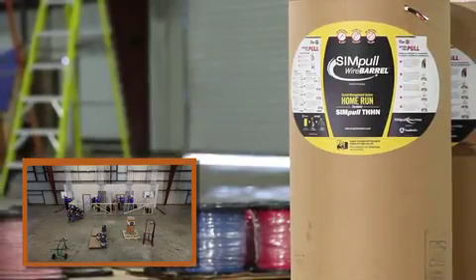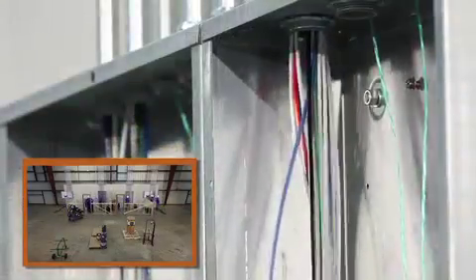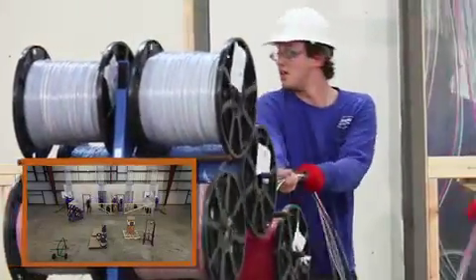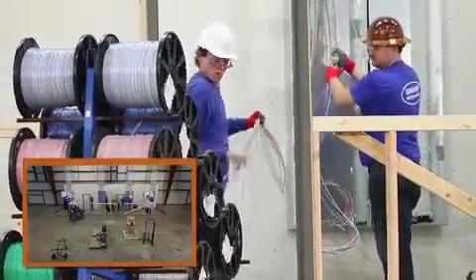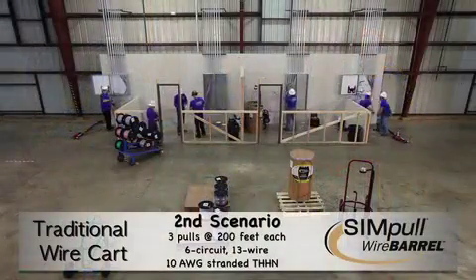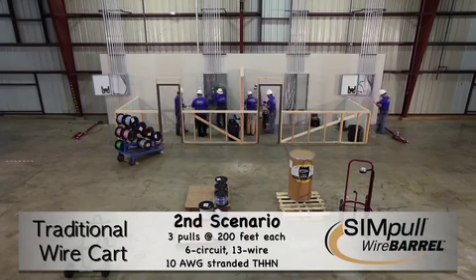During more extensive pulls, using the SIMpull WireBARREL system provides a fluid, consistent way to ensure all conductors are even and easy to group together as they are fed into the conduit. With the wire cart method, an extra man is needed in an attempt to create an efficient pull and keep the wires even as they are pulled off the reels and fed into the conduit. Considerable effort is required to pull the wire off all 13 2,500-foot reels. Repeating this effort throughout the day can lead to significant body stress and worker fatigue, which can negatively impact productivity and increase the likelihood of injuries.